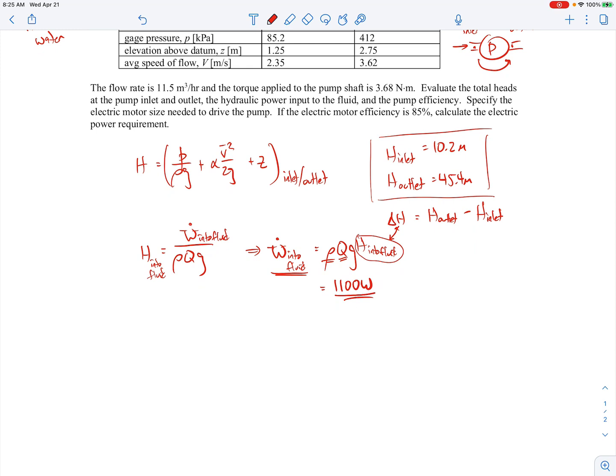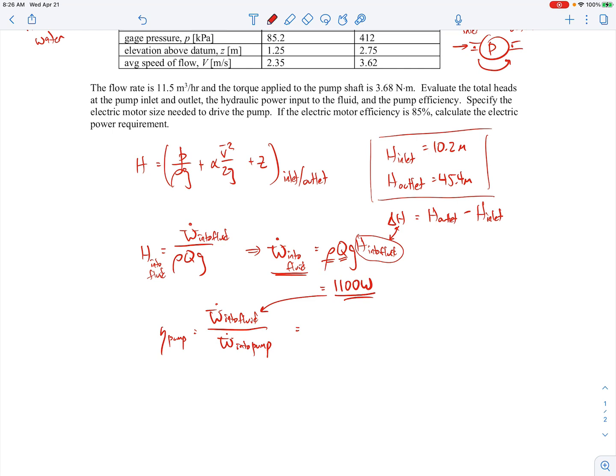The next thing we're asked to find is the pump efficiency. The efficiency of the pump is the power that makes it into the fluid divided by the power that we put into the pump. If it were 100% efficient, all the power put in would reach the fluid. The power into the pump can be found from the torque applied to the pump shaft, which is 3.68 Newton-meters, multiplied by the rotational speed of the shaft.